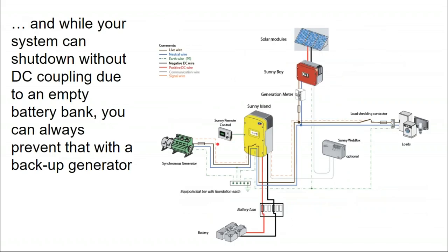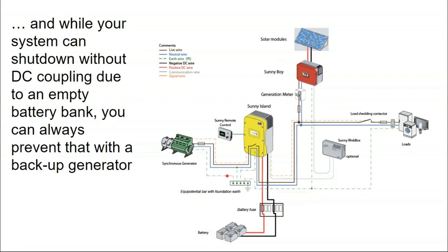Regardless of what you're doing, good design practice is to have another power resource on site, like a generator, which can help charge up the batteries in the event the system's fully discharged. On top of that, the Sunny Boy is a solar inverter with a dedicated AC output built in, which could be wired up to an AC charger to charge the battery. So there are many different ways to solve the black start issue without doing DC coupling.